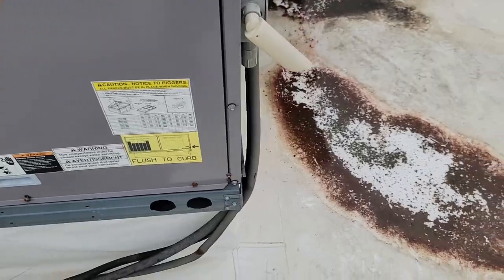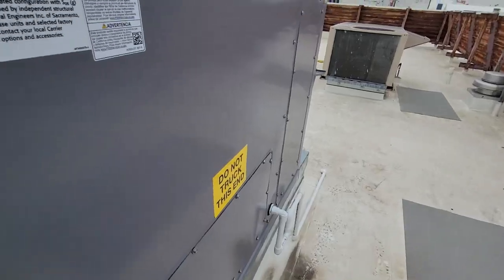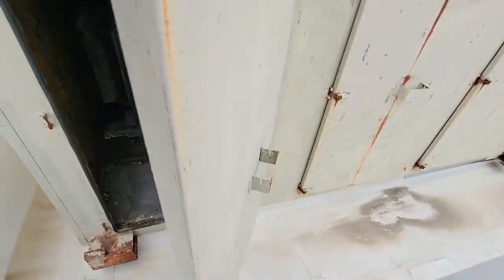We know this one's not it because it's shaking, rumbling, and has water in its trap. I should have asked them what area, but I don't think half of them would know. That one there's got water dripping out of it, so it's running. I think it's probably just a false alarm on the part of the alarm system company, because it's telling them they're having a smoke alarm and all this crap is running. Called alarm dispatch, asked them what it was — they got a trouble code. Got forwarded to their tech guy on call for the alarm panel company. He said a trouble code is different than an alarm code, and they would check it out on Monday. On to the next call.